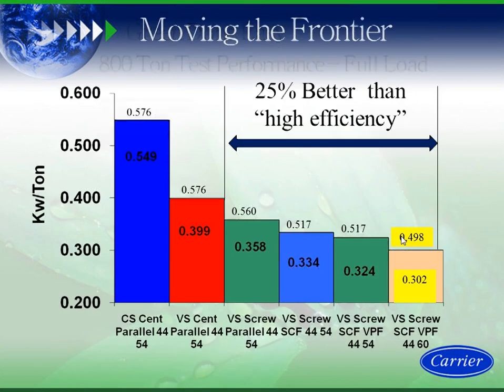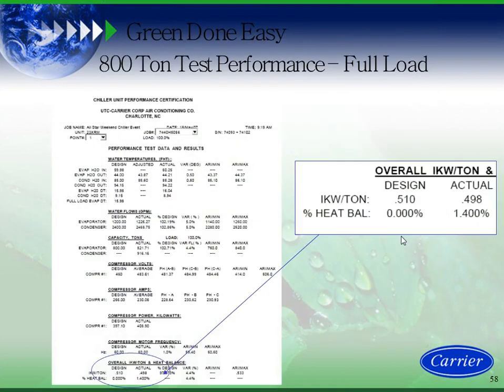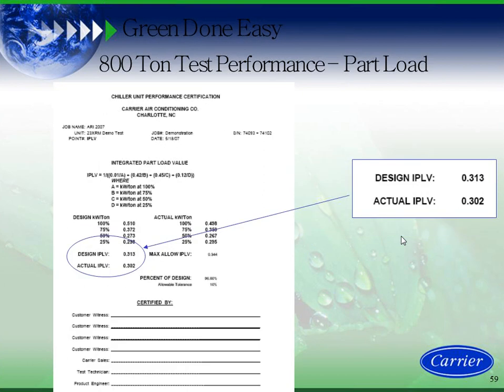And the reason why I could show you those pieces here is because we ran this in an actual test at 800 tons, and you can see there at the bottom, the design was 0.51. The actual came out to 0.498 when we ran this through a chiller test at our AHRI factory in Charlotte, North Carolina. And the part load design was 0.313. Actual kW per ton on that machine, 0.302.